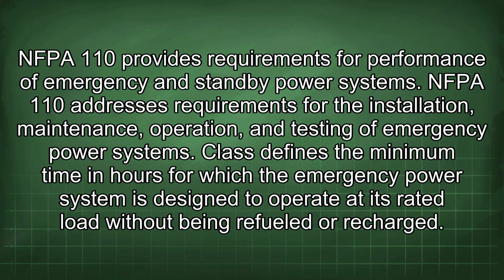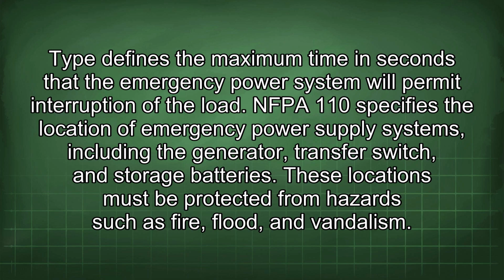NFPA 110 provides requirements for performance of emergency and standby power systems. NFPA 110 addresses requirements for the installation, maintenance, operation, and testing of emergency power systems. Class defines the minimum time in hours for which the emergency power system is designed to operate at its rated load without being refueled or recharged. Type defines the maximum time in seconds that the emergency power system will permit interruption of the load.